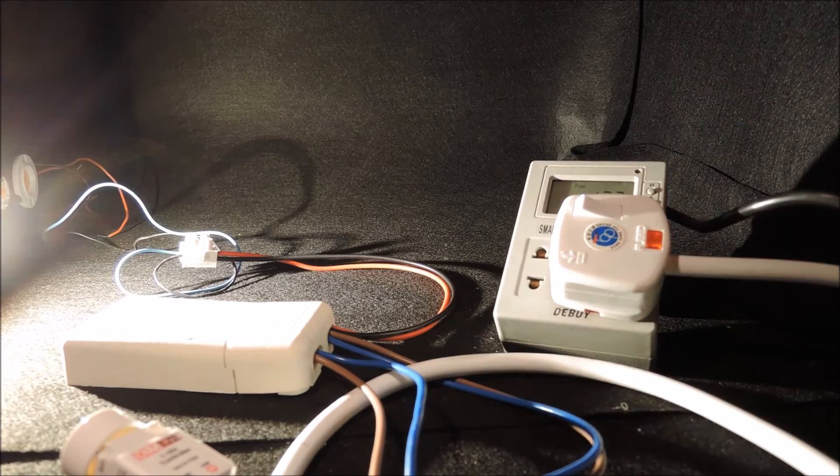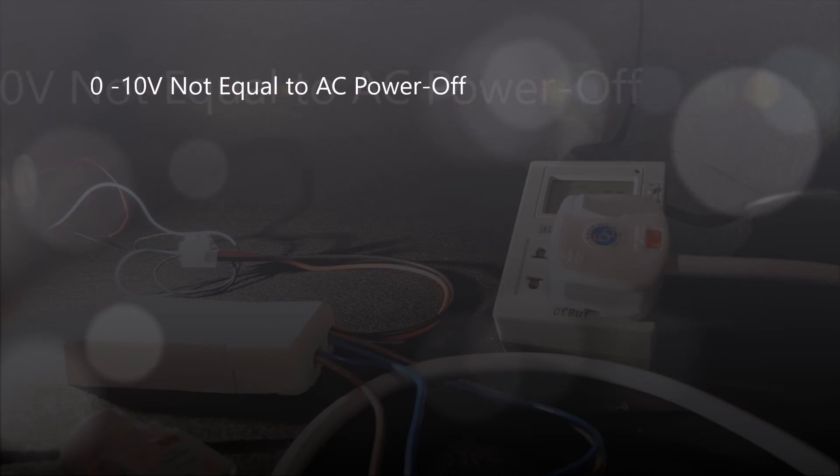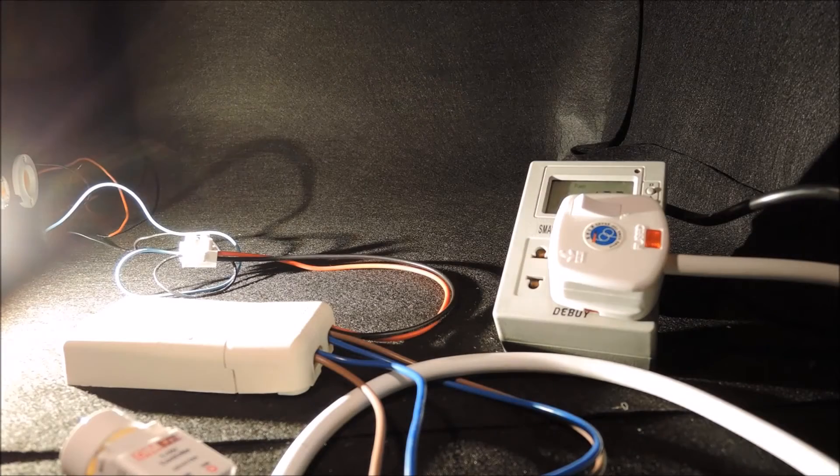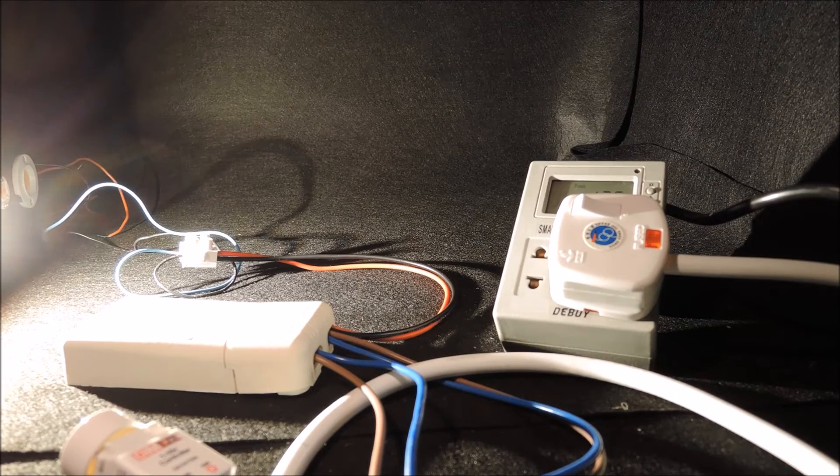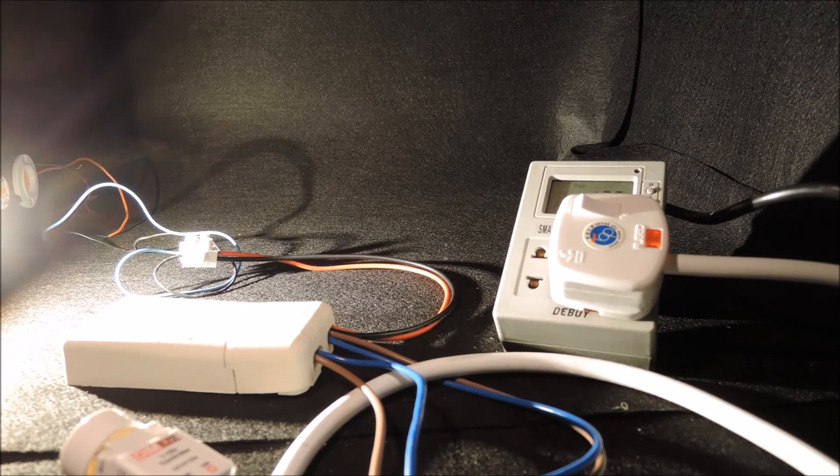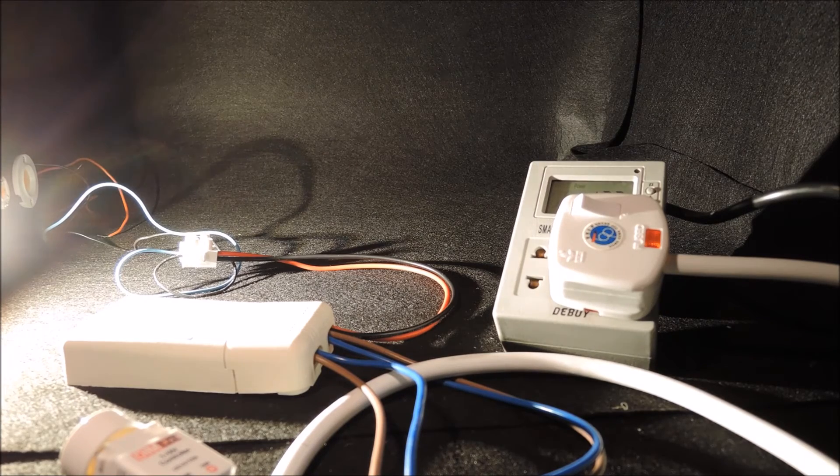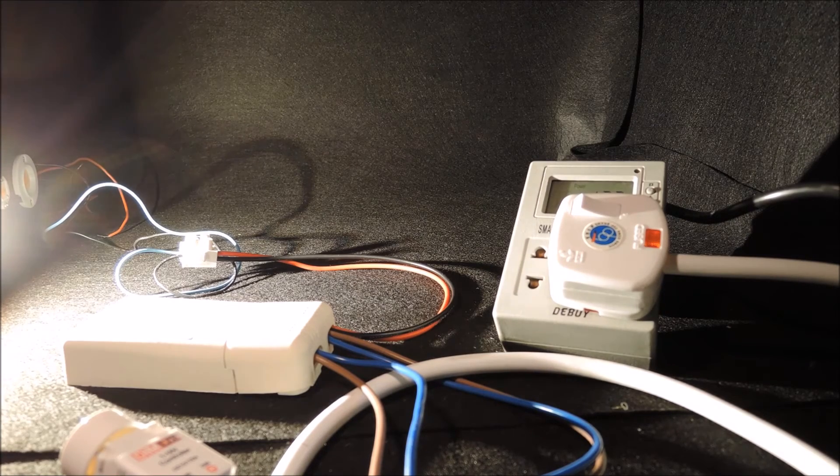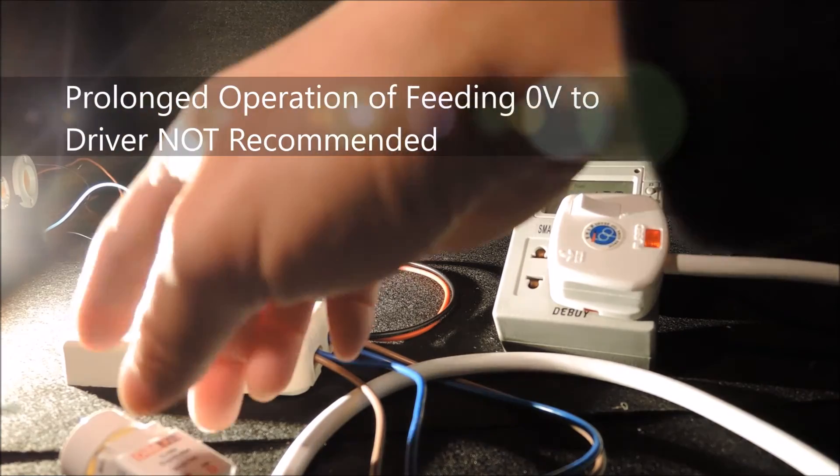This is what we have repeatedly commented on our website that the 0 to 10V dimmer has no equivalent to actually cutting off the AC power to the LED driver. Giving a zero-volt control signal to the driver is essentially the same as shorting the two input terminals, the dim plus and minus, together. In fact, prolonged operation of giving zero volts to the driver can cause driver failure after a period of time.